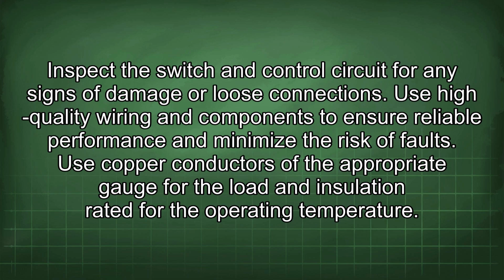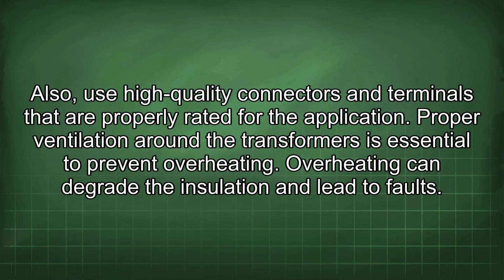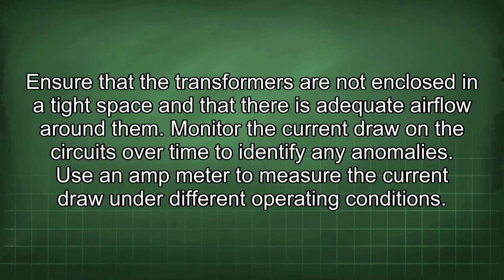Use copper conductors of the appropriate gauge for the load and insulation rated for the operating temperature. Also, use high-quality connectors and terminals that are properly rated for the application. Proper ventilation around the transformers is essential to prevent overheating. Overheating can degrade the insulation and lead to faults. Ensure that the transformers are not enclosed in a tight space and that there is adequate airflow around them.